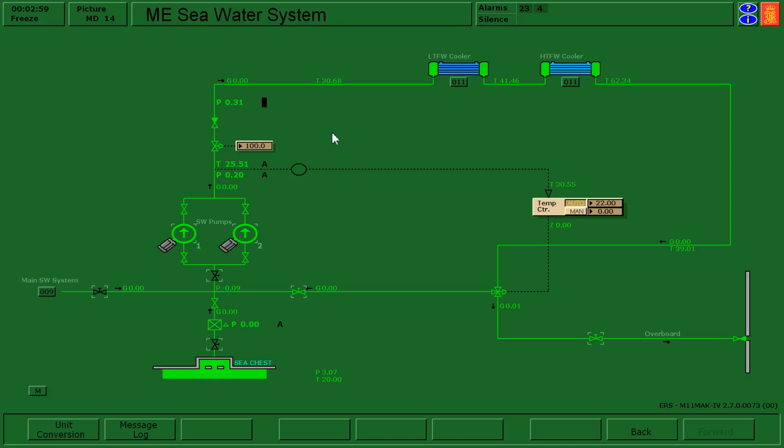The other thing that it does is it alerts all of the other workers in the plant that now somebody has acknowledged that there is a problem and will be looking after it. Ultimately, you may not be the person that solves it or troubleshoots it, but you are now in charge, and until you give that responsibility to somebody else, you are in charge of making decisions on this alarm. Good news is that we have a good idea what the problem is. Low pressure coming out of the pump, and we have some blockages, so we're going to be able to solve this alarm.